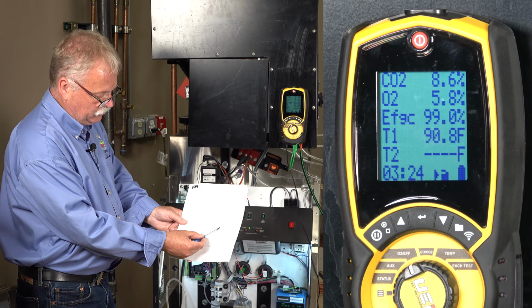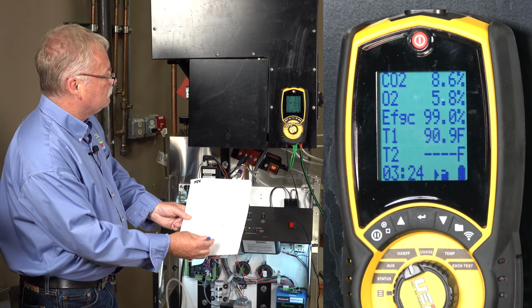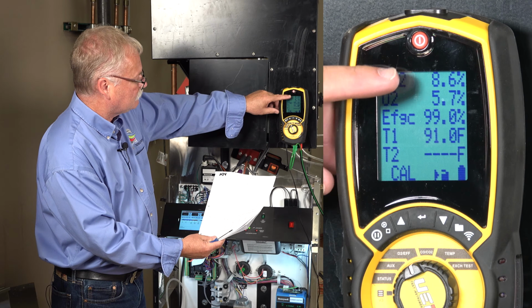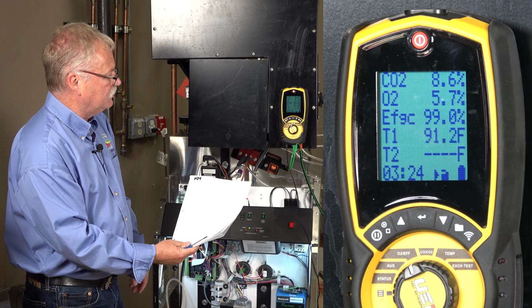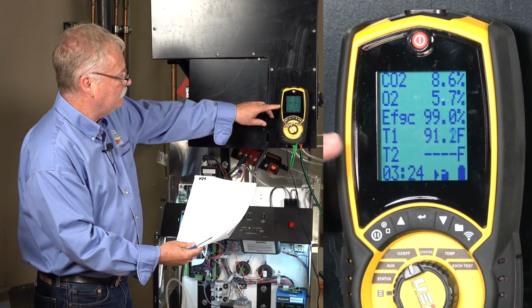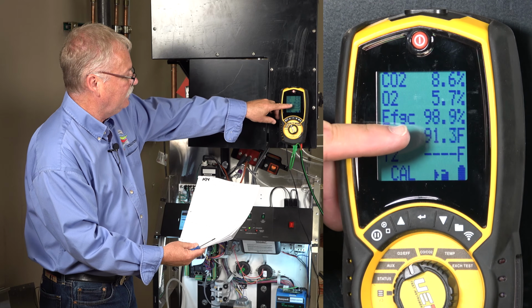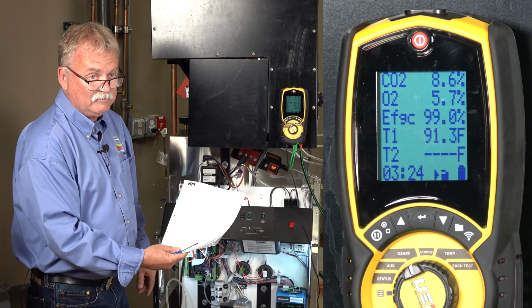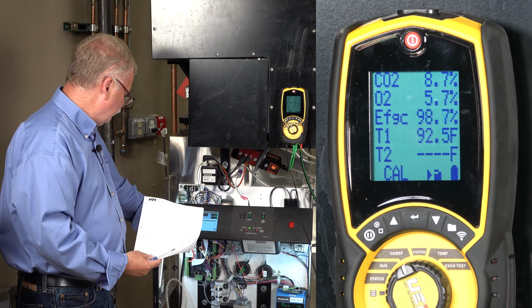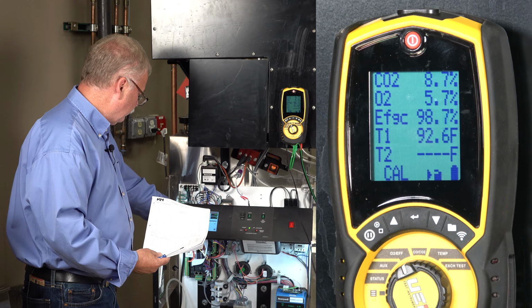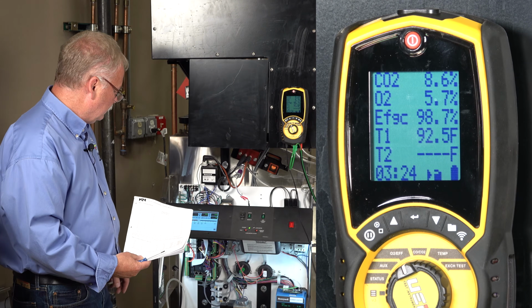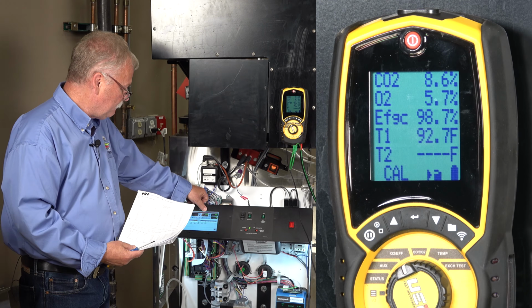Plus or minus 0.2%. 8.6, I'm probably just a little bit low at this point. But as you can see, my efficiency technically is 99% efficient. If I want to go to high fire, I'm over here, this adjustment button. Now you're going to hear the boiler ramp up.